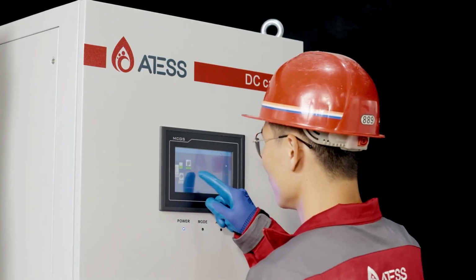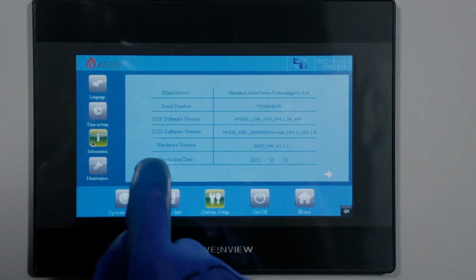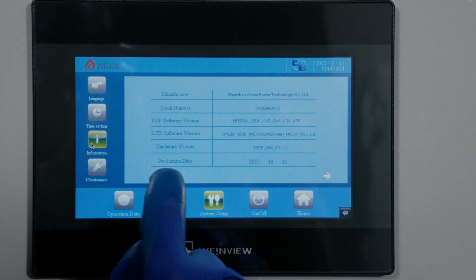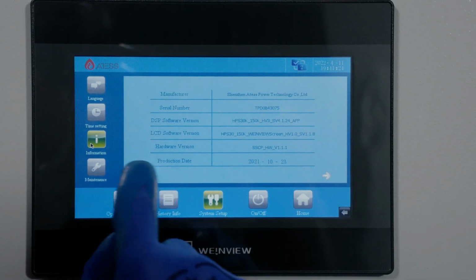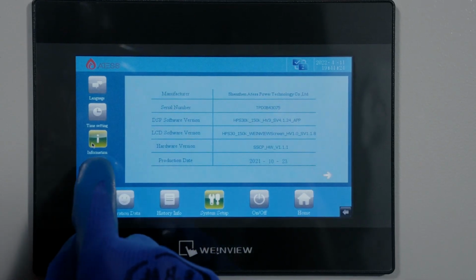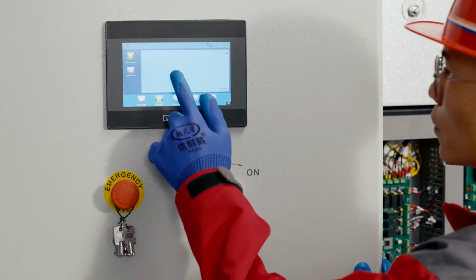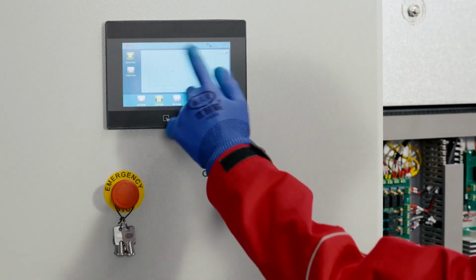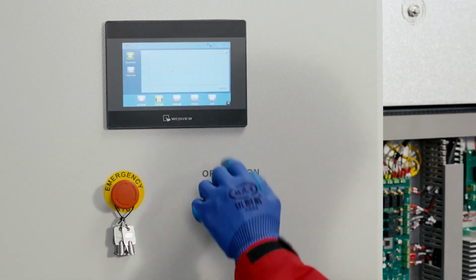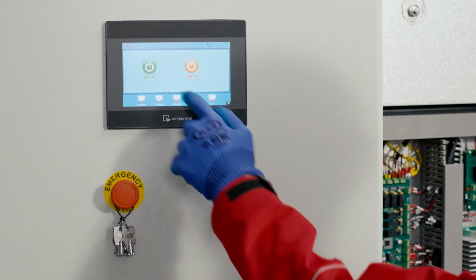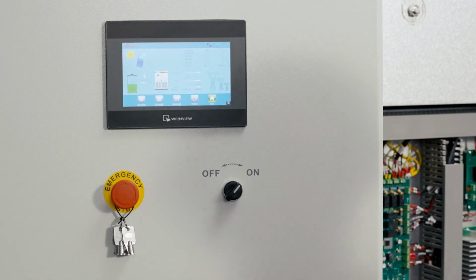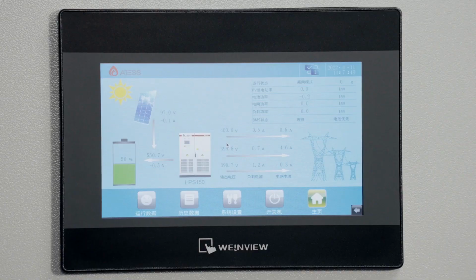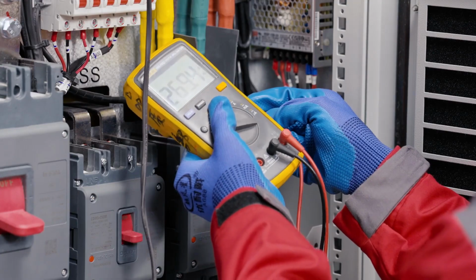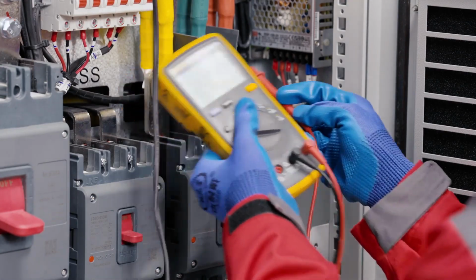To set the parameters, first of all we need to check the device software version. If there is no version information, it means HPS has not been programmed. Check the fault page information. If no fault is detected, turn the black knob first, and then click the power button on the screen. When the device is to be started, ensure that the bypass breaker is off. After 60 seconds, when the system self-check is completed, check whether the output voltage is phase-to-phase 400 volts.